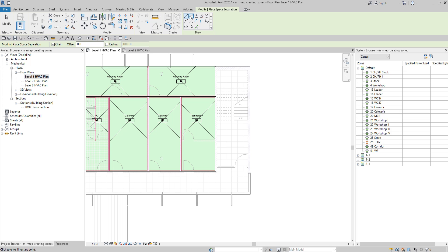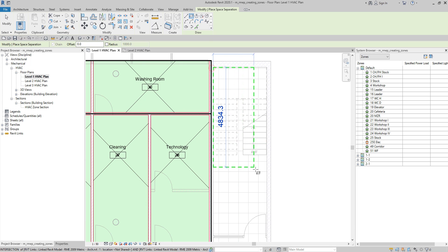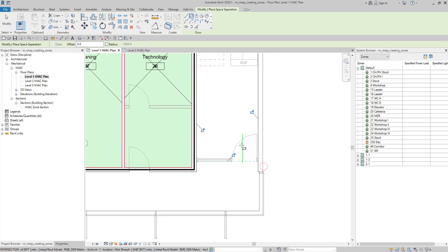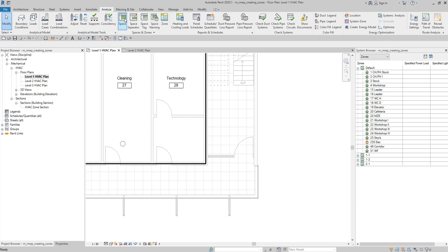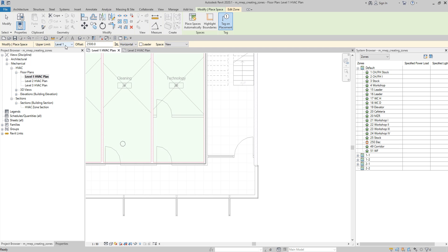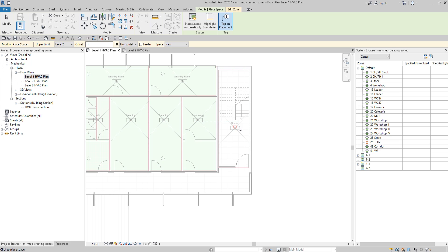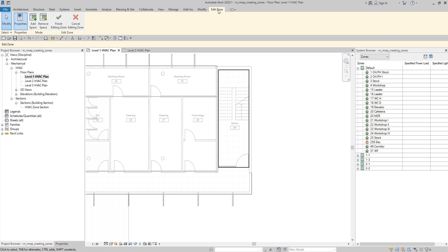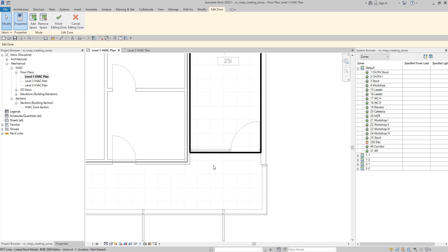I select the space separator and create the boundary lines. Then I try to create the space again within the zone tool. I go to Analyze, select space, set the upper limit to level 2 with an offset of 0, and place it. I then escape once to exit the space tool — but not to terminate the zone tool — and then open the level 2 HVAC plan to continue adding spaces on upper levels.